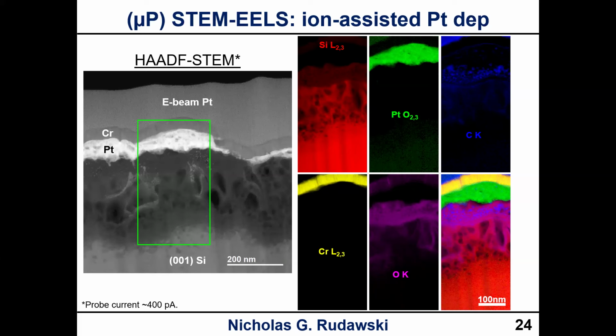And that's exactly what we would expect, just like we were doing with the EDS. This was with about 400 picoamps of current, so not quite as high as what we were using before. Generally speaking, you don't need as much current when you're doing EELS compared to EDS, because your signal to noise in your maps tends to be better, which again could be a topic for another discussion at some point. But anyways, I wanted to show you an example of microprobe STEM EELS as well.